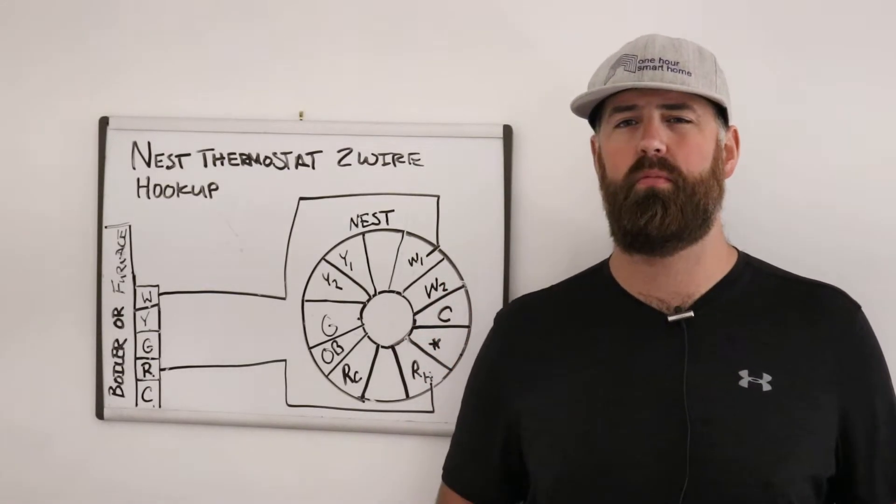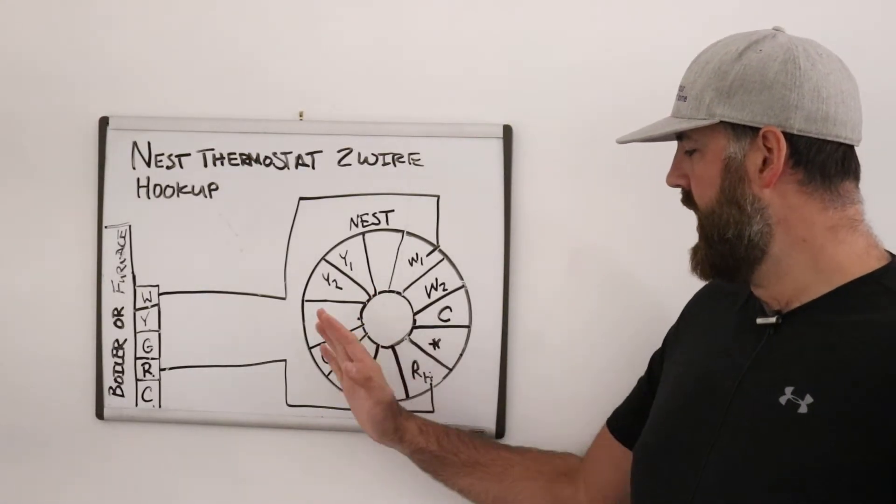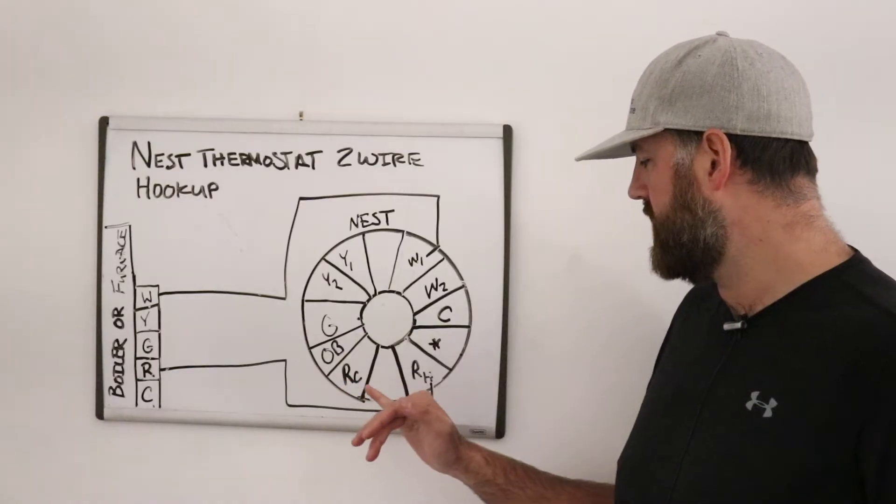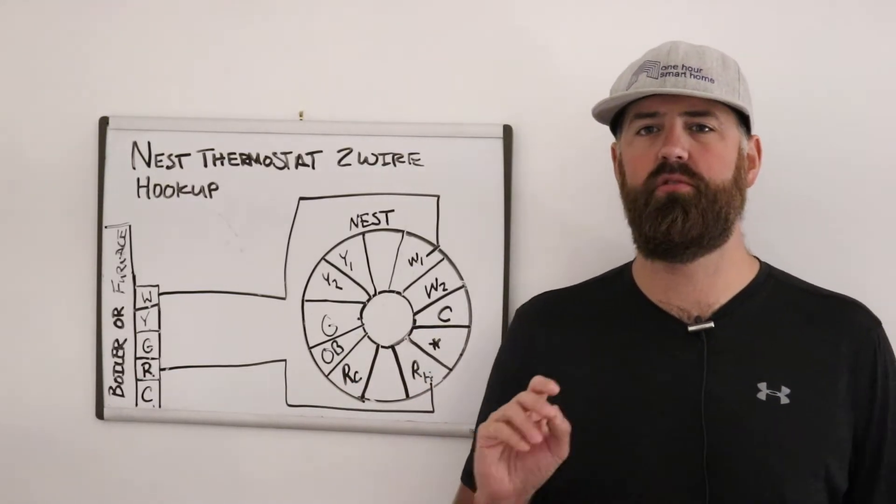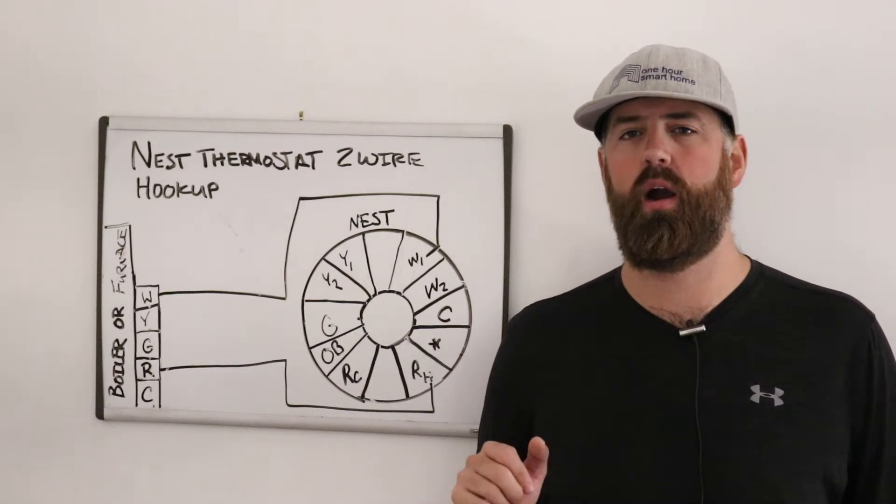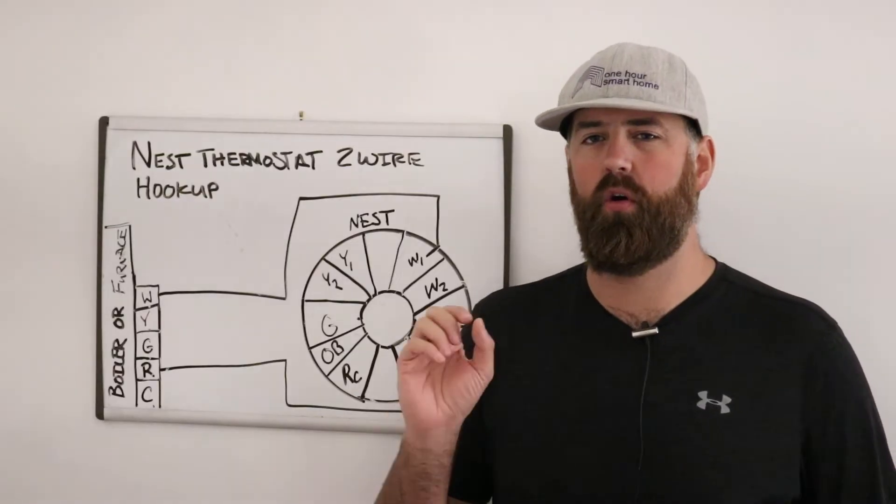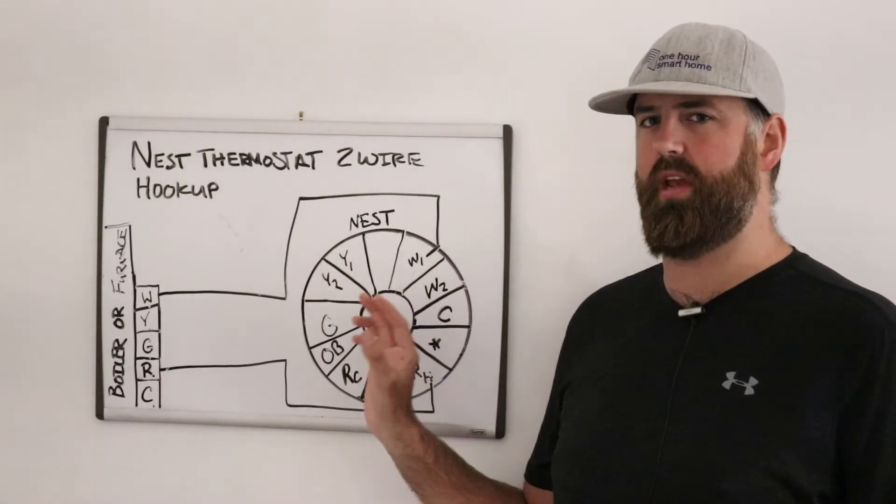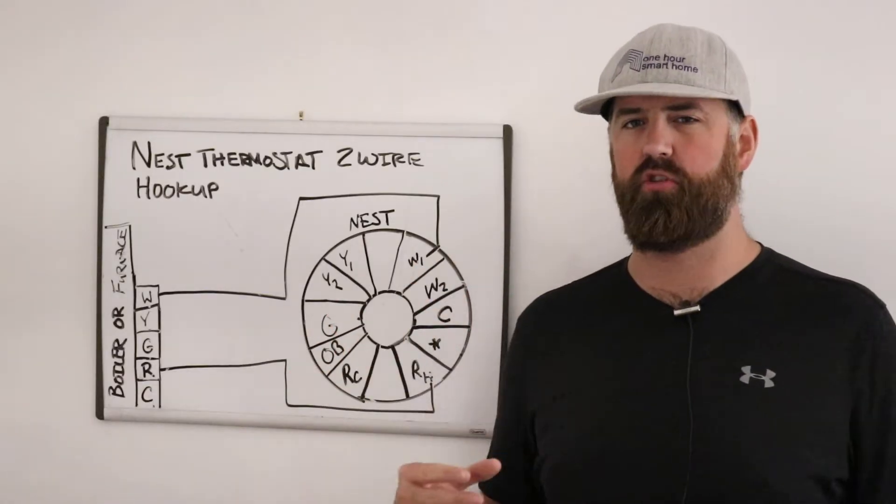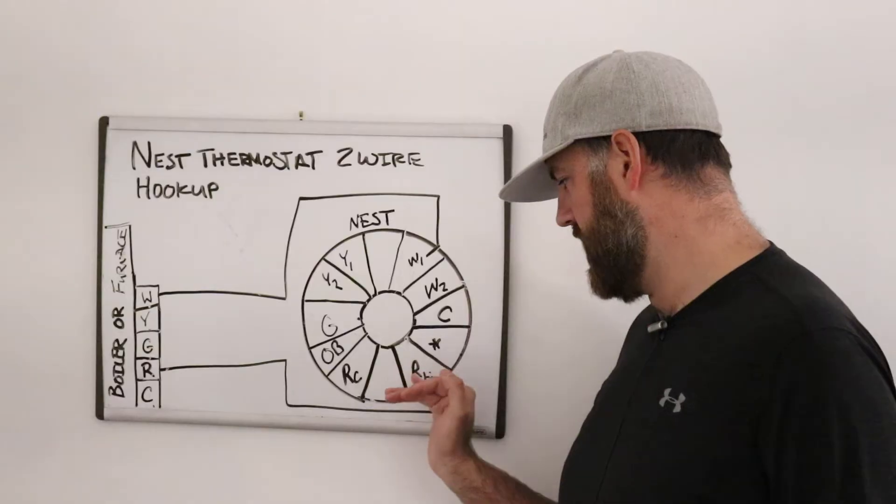Now a lot of you are probably going to have an old thermostat which may have had RC and RH and a jumper wire between them. On the nest you do not need to have a jumper wire between RC or RH. That is only for your old style thermostat. That jumper wire is done internally in the nest like in its circuitry. So there is no actual need for a physical jumper wire on RC and RH.